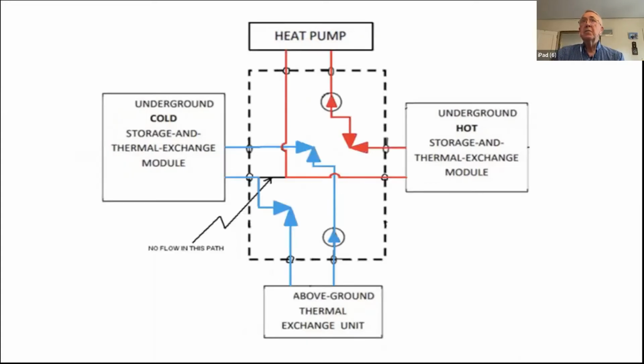So moving along, here's an example of settings of the valves to show what's going on in the coldest winter night. This follows the example of the system from Belgium. So what we're doing is we've got very cold water from the above ground unit feeding into the left-hand ground loop. We got nice warm water from the right-hand loop feeding into the heat pump, giving very efficient heating for the building.